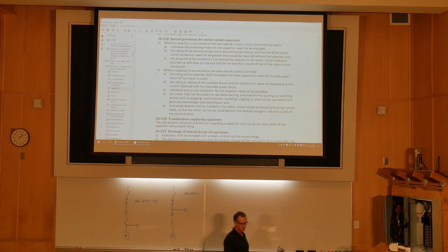It says, where a capacitor is connected on the load side of a motor controller, the rating of the capacitor shall not exceed the value to raise the no-load power factor of the motor to unity. So manufacturers have power factor correction capacitor charts for selecting them for motor horsepower. So that's a statement really for engineers on design. You don't have to worry about it. You're not going to have to size the capacitor. They're just making you aware of that.